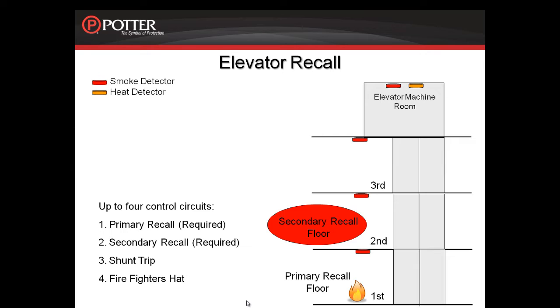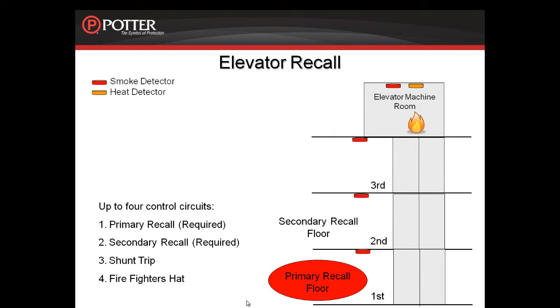When talking about shunt trip, shunt trip will trigger a relay that will indicate to the elevator controller that they need to kill the power to the elevator prior to the sprinkler head opening up in the elevator machinery. Therefore, the shunt trip relay is triggered when the heat detector in the elevator machine room activates. When that heat detector activates, we also want to recall the elevators to the primary floor of recall, which is the first floor.